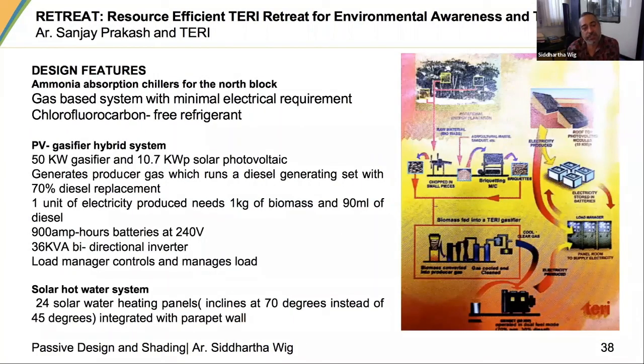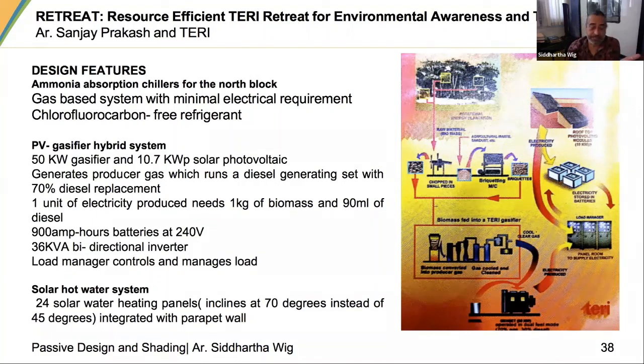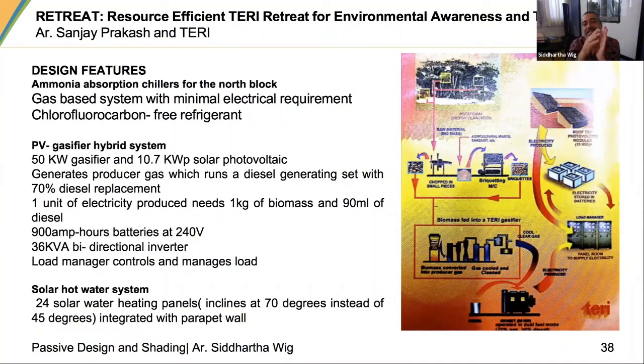Once the amount of required energy was reduced, they used a gas-based ammonia chiller, a gasifier using biomass generated at site, and a solar hot water system. What I found interesting was that the solar hot water system was installed far more vertically than the conventional angle for Delhi. In discussions I learned that this increases effectiveness in terms of space usage — it can be used on the elevation, and maintenance becomes easier because less dust settles on more vertical glass.